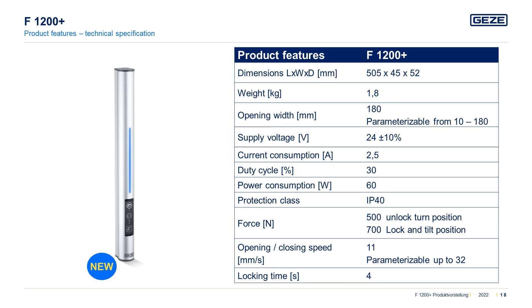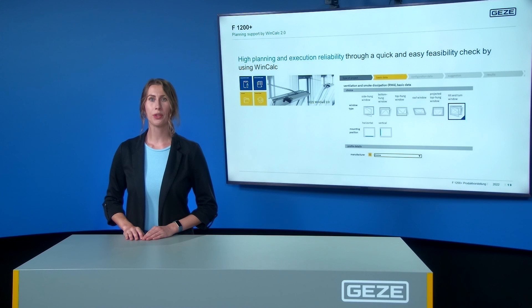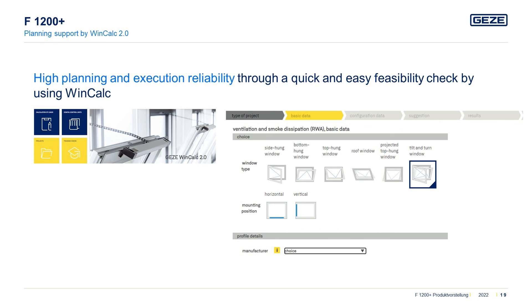The technical data of the F1200 Plus: the opening width can be customized and individually adapted from 10 to 180 mm. Standard Protection Class III is realized due to an opening width of less than 200 mm. It is a 24-volt window drive designed for indoor use. The force of the drive is between 500 and 700 Newtons to move large and heavy windows, and the locking time is 4 seconds. The F1200 Plus has been integrated into WinCalc to provide the best possible planning support.